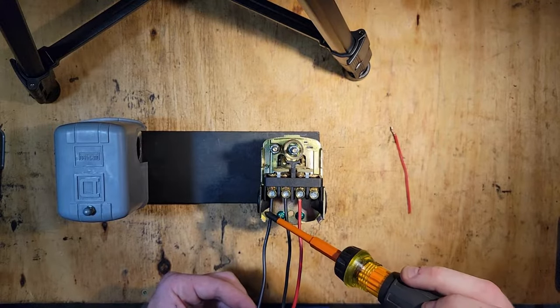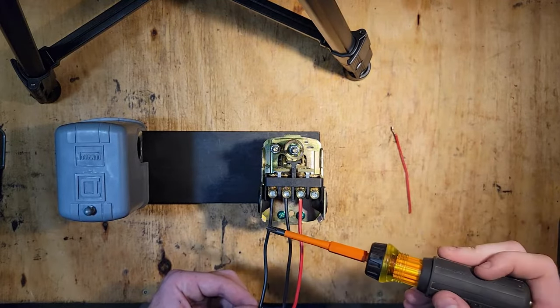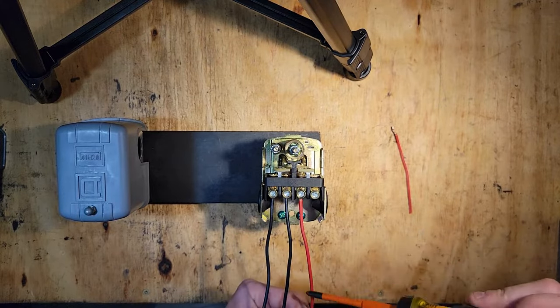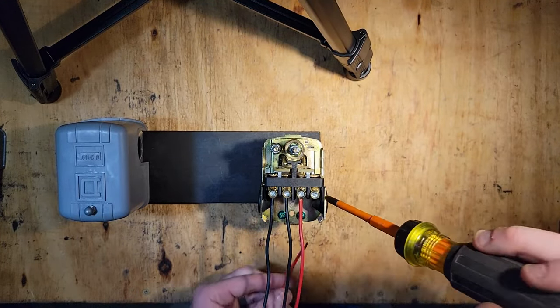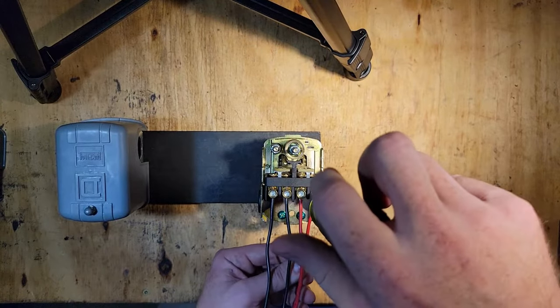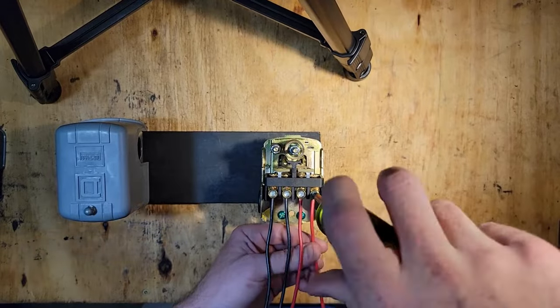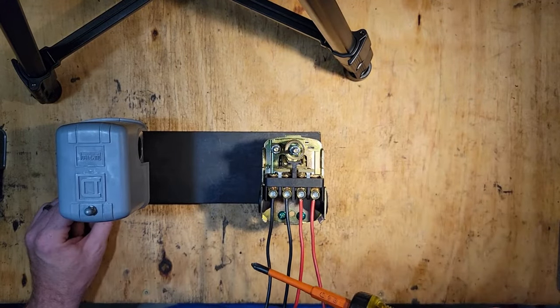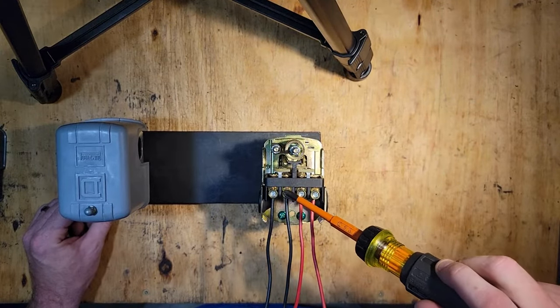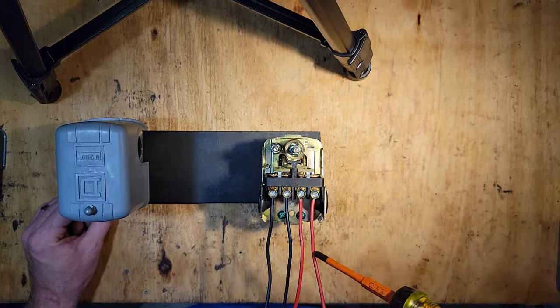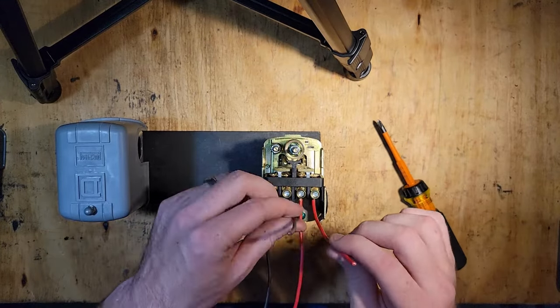In this situation, I'm going to have a hot from my breaker. Speaking of 240 volt, I have a hot coming on one side and then another hot coming in on the opposite side. Then the adjacent one to each will be what goes to your control box. So we'll have power coming in from a breaker, power going out to the control box, power coming in from the breaker, power going out to the control box.